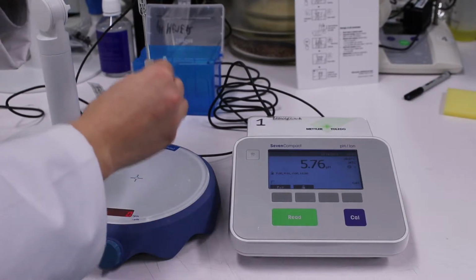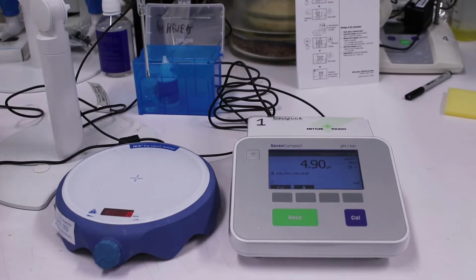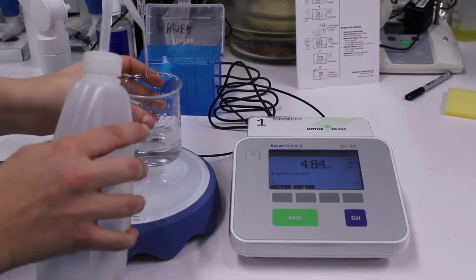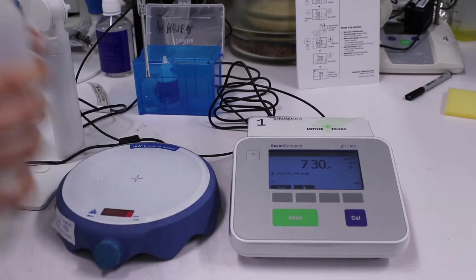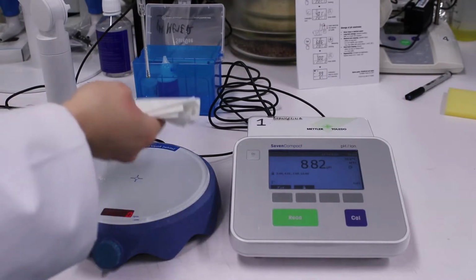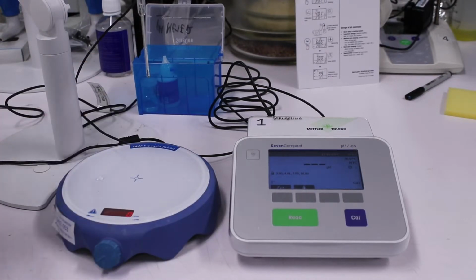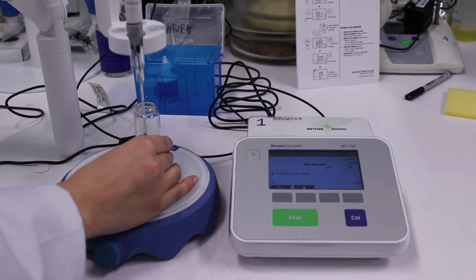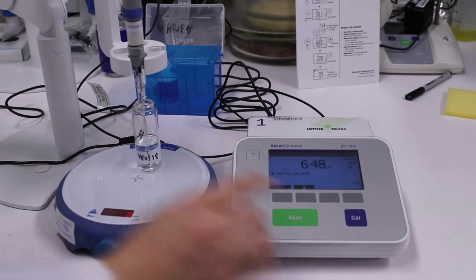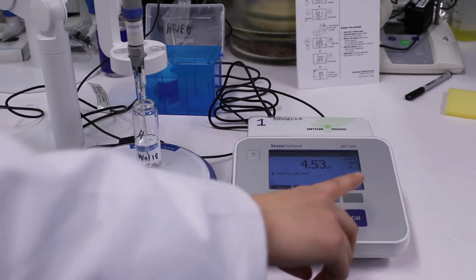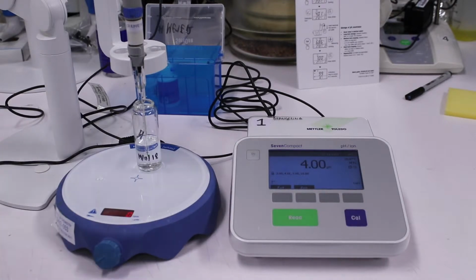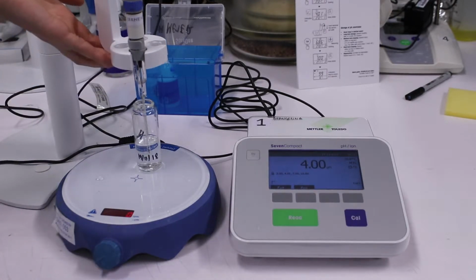To start with, you're going to gently remove the cap and rinse the electrode with deionized water. Once you've done that, you can gently dab it with a paper towel and then submerge the electrode into the first solution. Then press Cal. This should now read Cal 1.